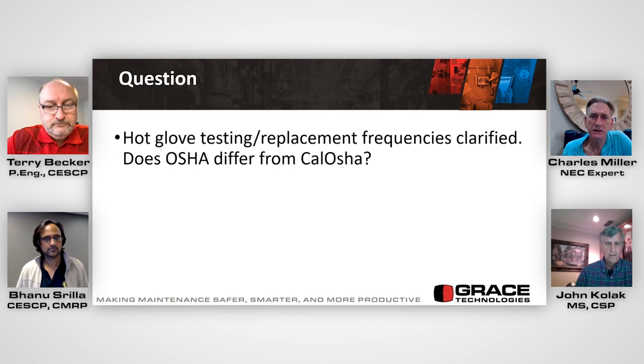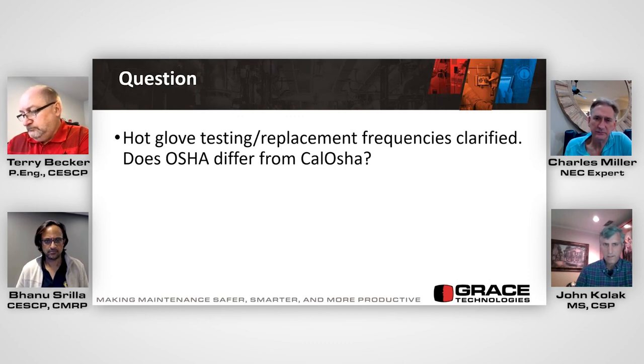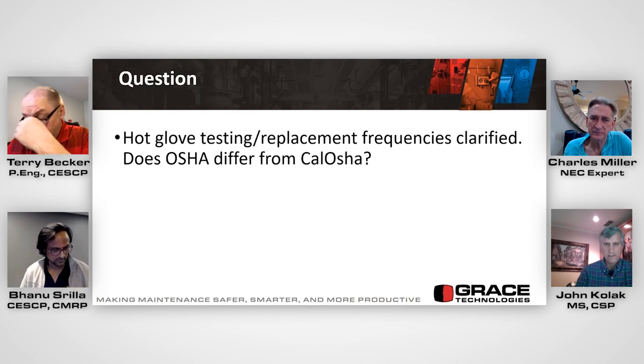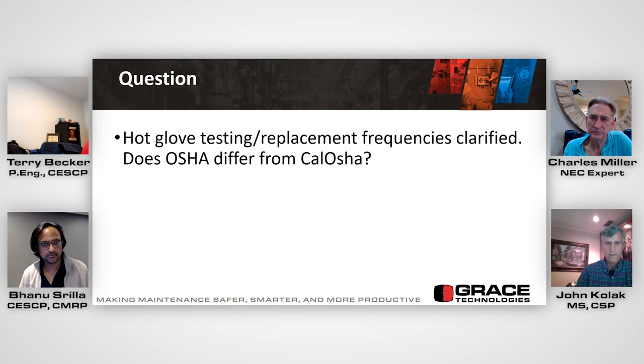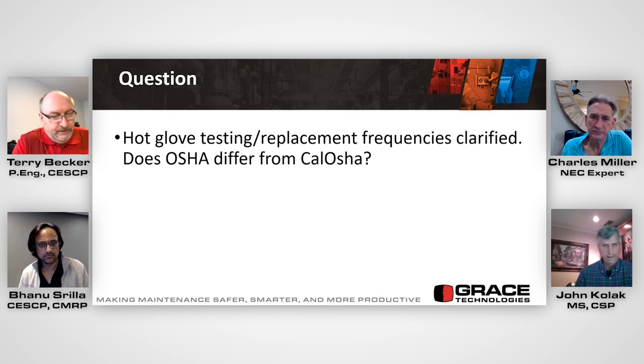Well, theoretically, the state-run OSHA programs are supposed to be at least as rigorous as the federal standards. With Cal OSHA, my experience has been that's not true, especially in the high voltage orders that they have. That being said, I think the testing requirements remain the same, that every 6 months they have to be tested. But if I'm wrong about that, that's a good interval - just whatever the local agency's interval is, that's all that's required. But if you send the gloves in every 6 months for a laboratory test, and air test them each day when they're in use, you're going to be just fine.